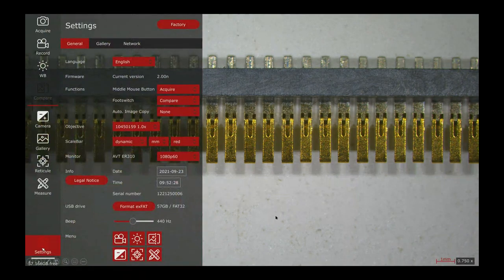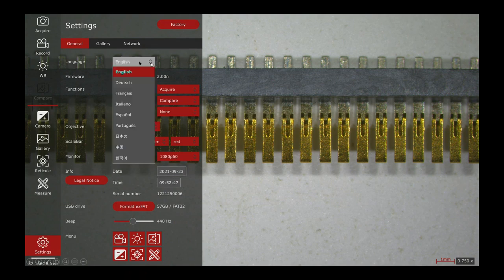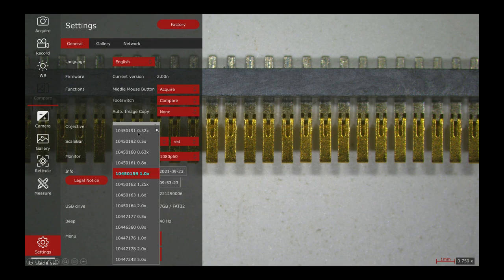So the first thing that you have to do when you start Emspira 3 is you go into the settings menu, and here in the settings, you see it opens with English, but if you click on language, you can choose out of many languages, including German, French, Italian, Spanish, Portuguese, and I guess Japanese, Korean, and Chinese. The next thing you do to make Emspira 3 operational is out of this list of objective numbers here, you choose the objective that you're actually using. So then the calibration data for this objective will be used for further use inside Emspira 3.